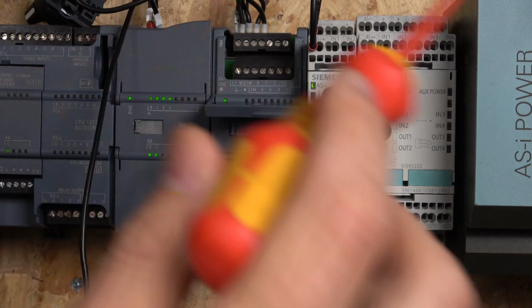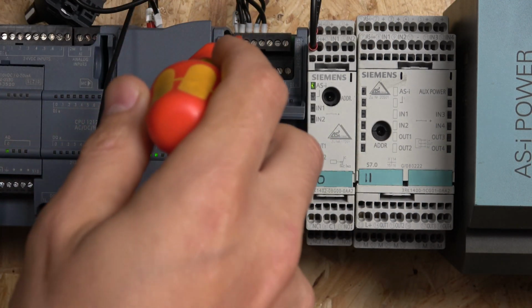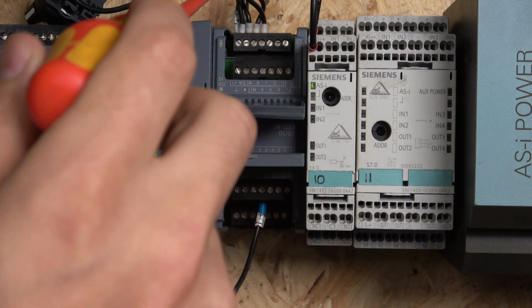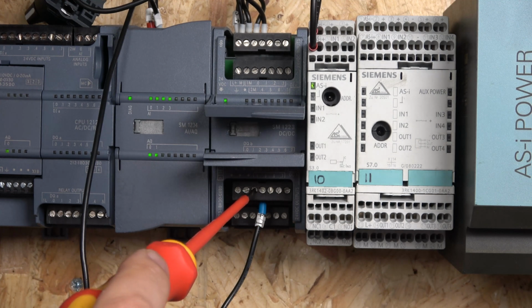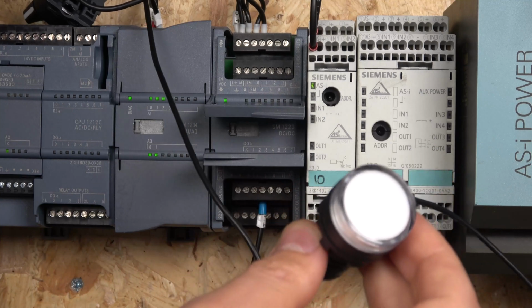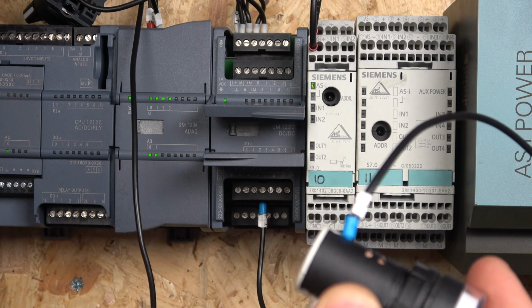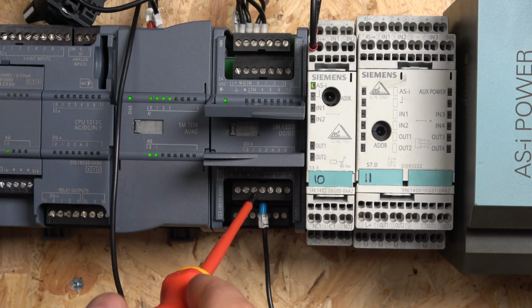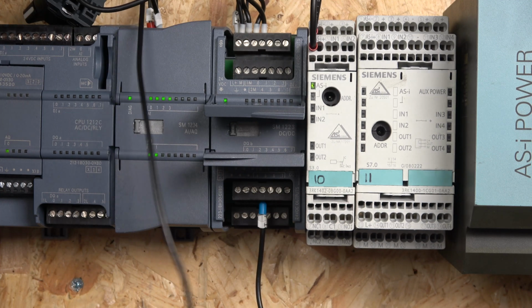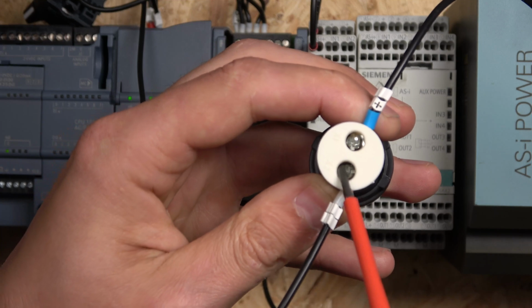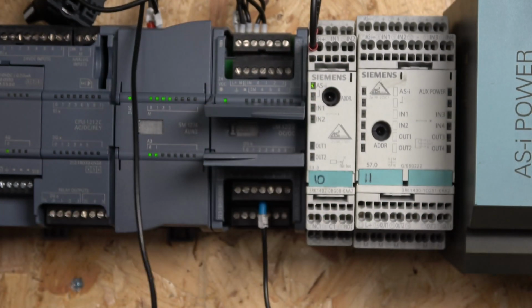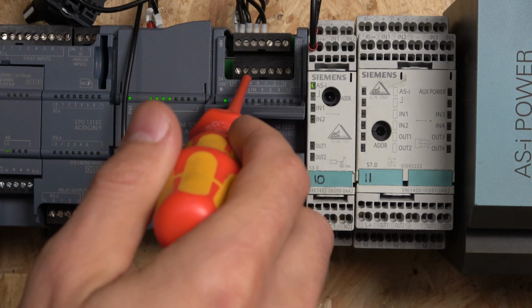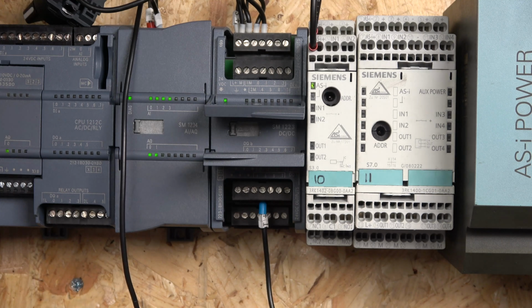But the key is to remember, which we're going to show at the end of the video, to watch out that this M in here is your neutral for wherever this 24 DC is going. As we can see, we've got the light bulb in here, which we're going to check out in a minute. It has 24 volt DC going to it, which is going to be output from our first output on this card, and it does require the negative, which is going to be my X2 in here. It must come from the same power supply that is powering this card itself. If it comes from a different power supply, it will not work because this neutral does not come from the same point. So do bear that in mind. We're going to be doing testing, and I'll show what happens if you get a different negative from a different power supply.